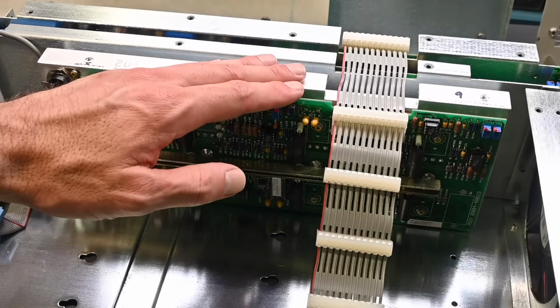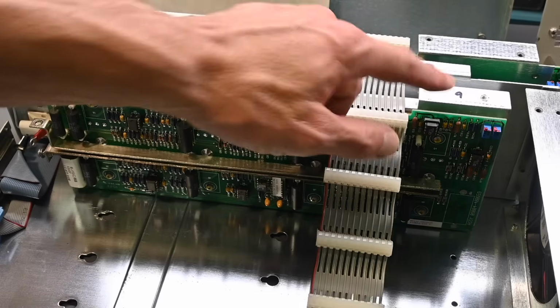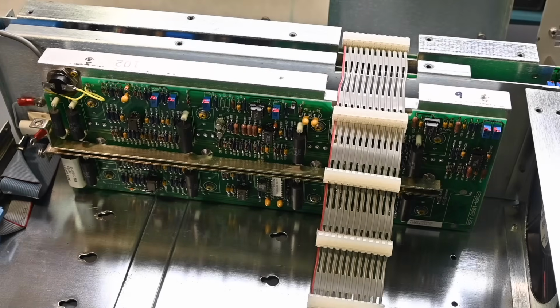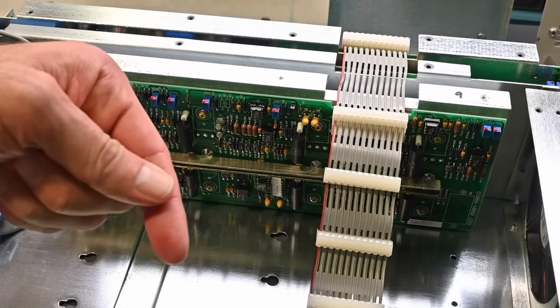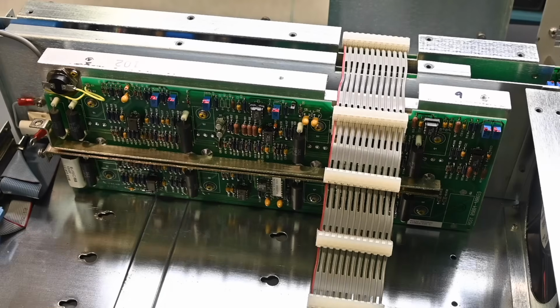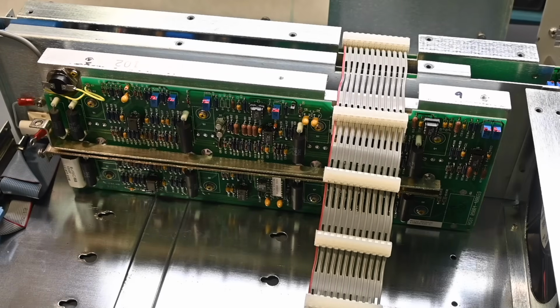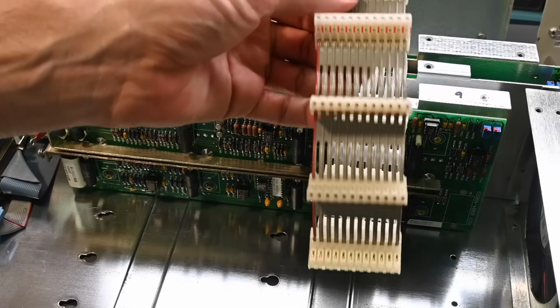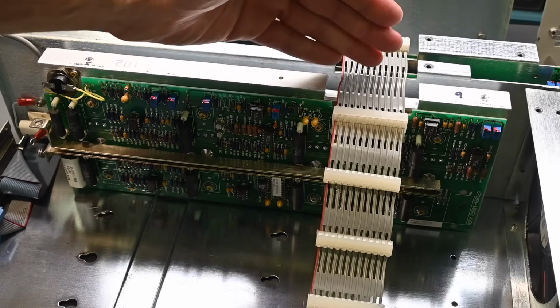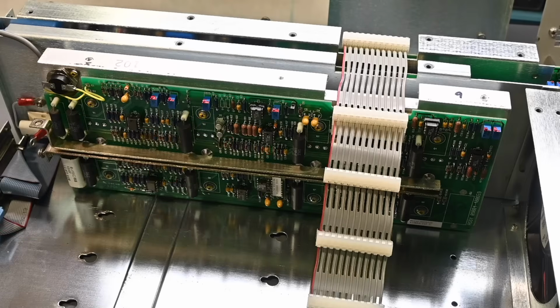All right, the first module is in place, and you can see I marked this module as 9. The reason for that is because when I was removing the modules, I started on this side and just worked across that way. Now all the modules are electrically identical. They all work in parallel, so they could be installed in any position. The electronic load is going to work perfectly fine. You can see this ribbon cable that ties all the modules together.